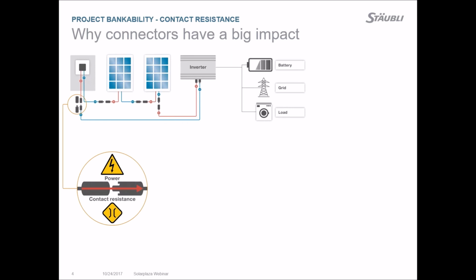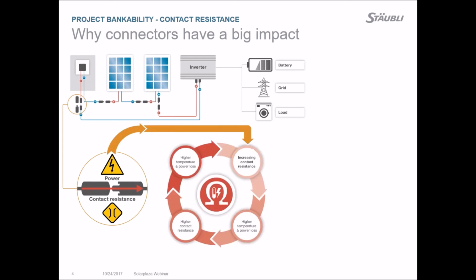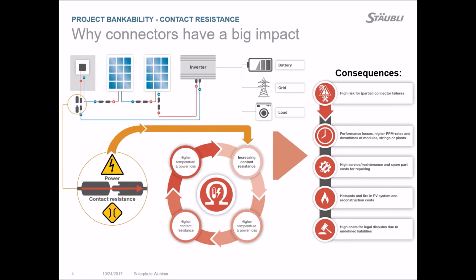So the key to efficient operation and energy feed-in is long-term reliability related to cabling and connectors, on a constantly low contact resistance. Vice versa, an increasing contact resistance inside the connectors induces higher temperatures and power loss, which then increases the contact resistance again, creating a spiral resulting in high risk of partial connector failure.